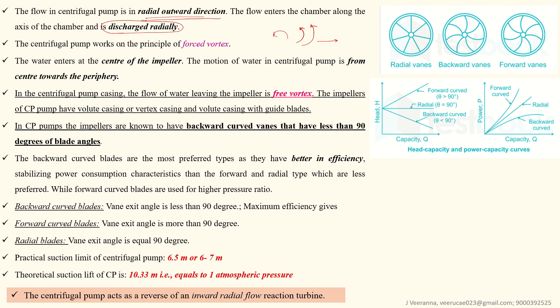The centrifugal pump works on the principle of forced vortex. Water enters at the center of the impeller, called the eye — not from the sides, bottom, or top. The motion of water is from the center outward to the periphery. As water moves from the center, pressure acts outward toward the periphery. Water inside the impeller experiences forced vortex; water leaving toward the casing is free vortex.